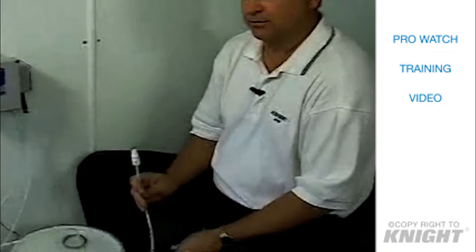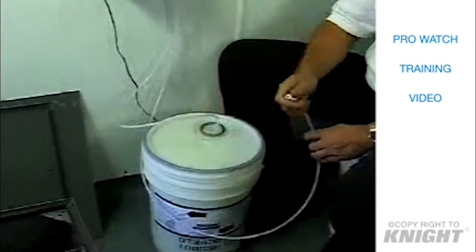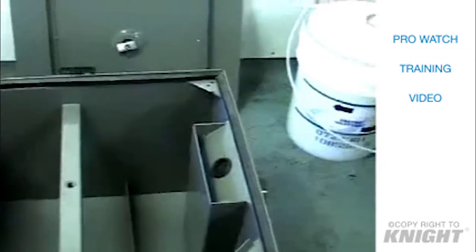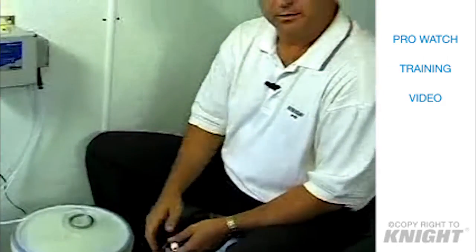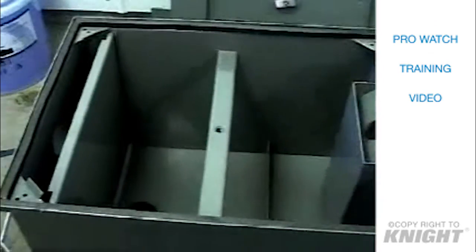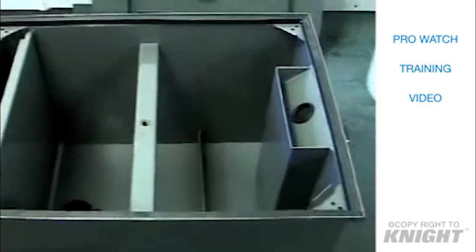When selecting a location to inject the grease trap digestant, be sure to inject upstream of the grease trap. Obviously, it wouldn't do you a whole lot of good at keeping the grease flowing through the system if you were to plumb it on the discharge side. Most grease traps are installed in a drain line typically that is not near a dishwasher, because hot water and/or chlorine or sanitizers will kill the enzyme and eliminate the process of the enzyme breaking down the grease. So anywhere upstream of the grease trap, typically we'll treat the trap with your products in an effective manner.